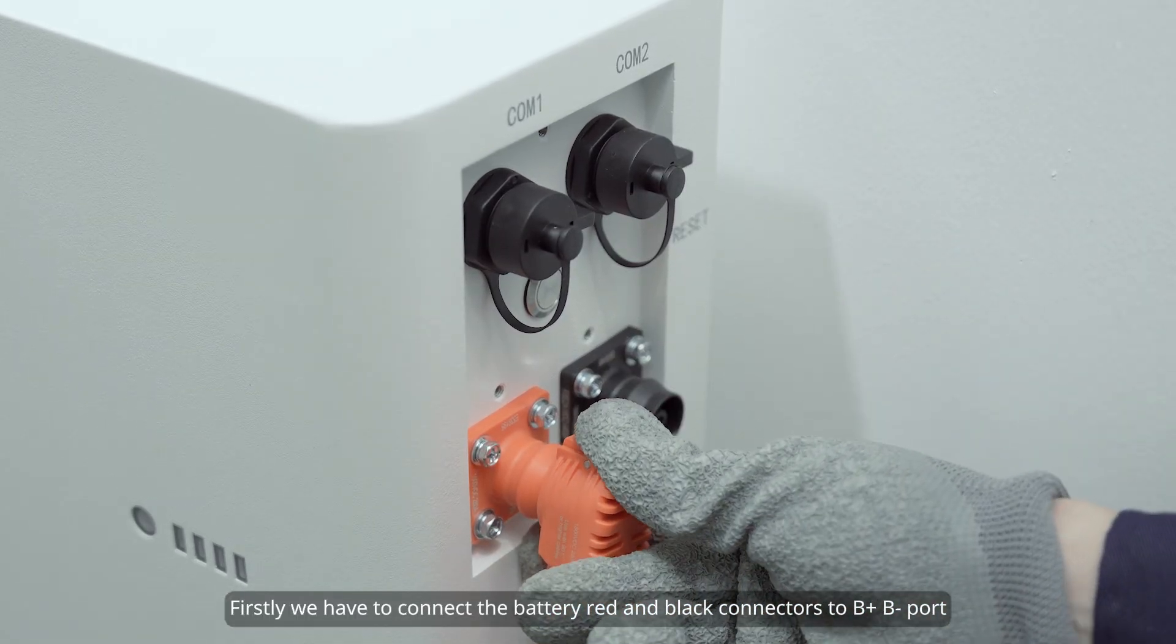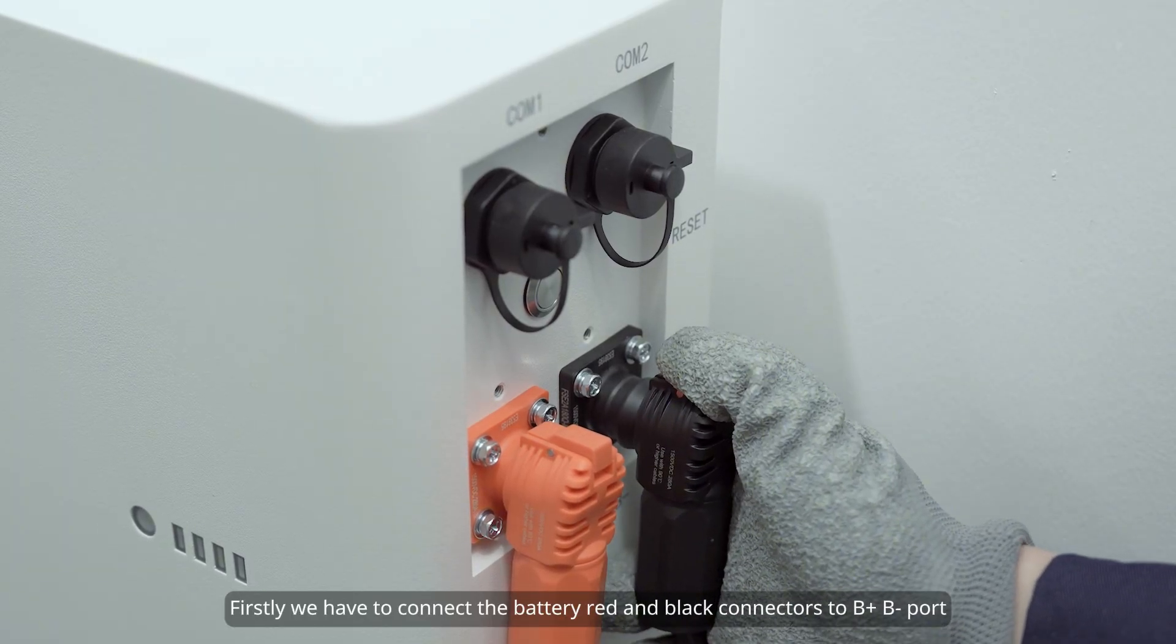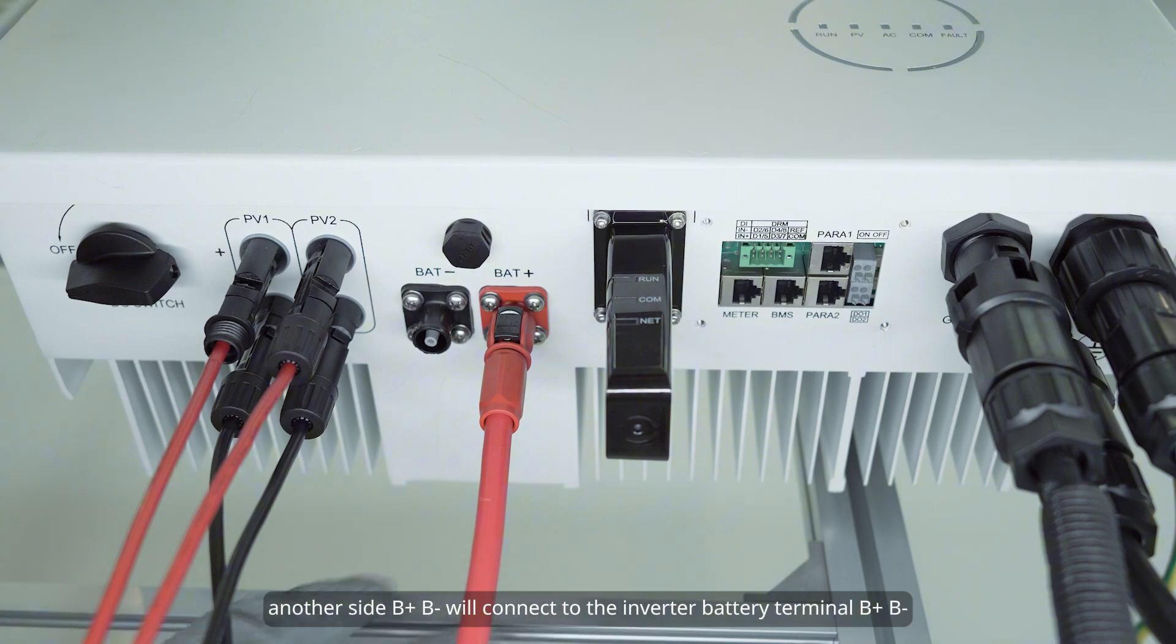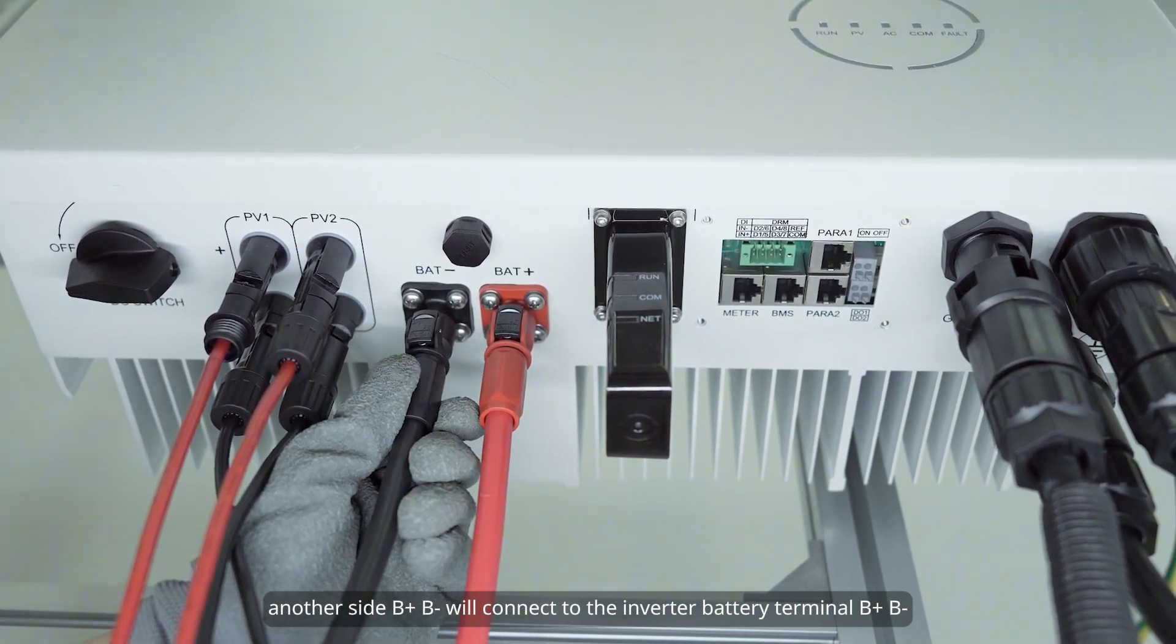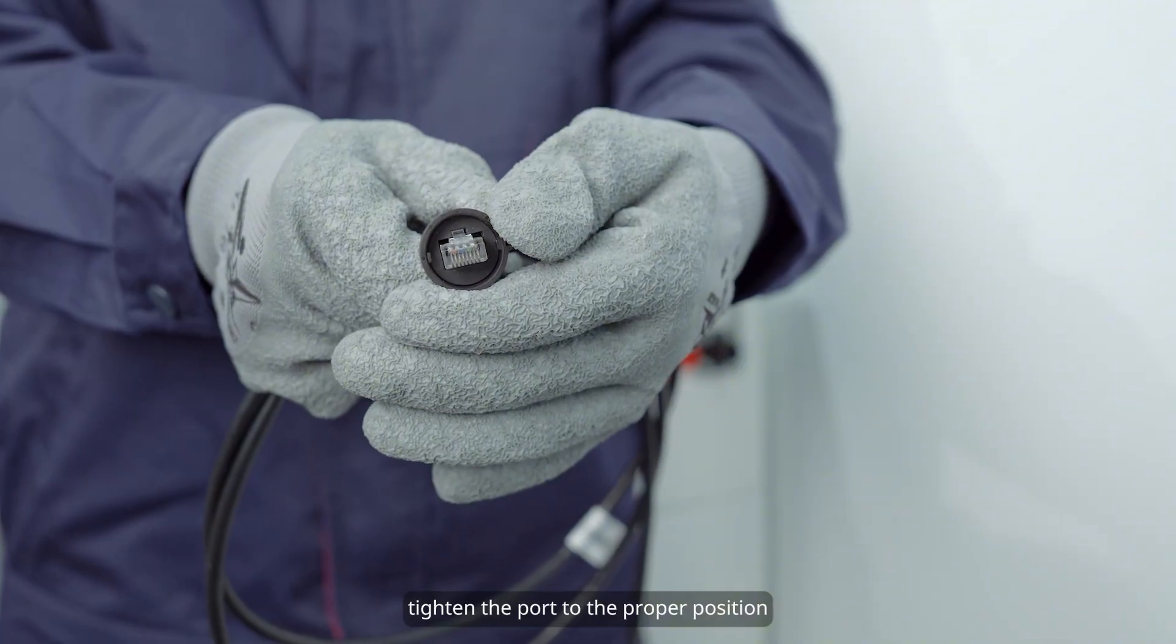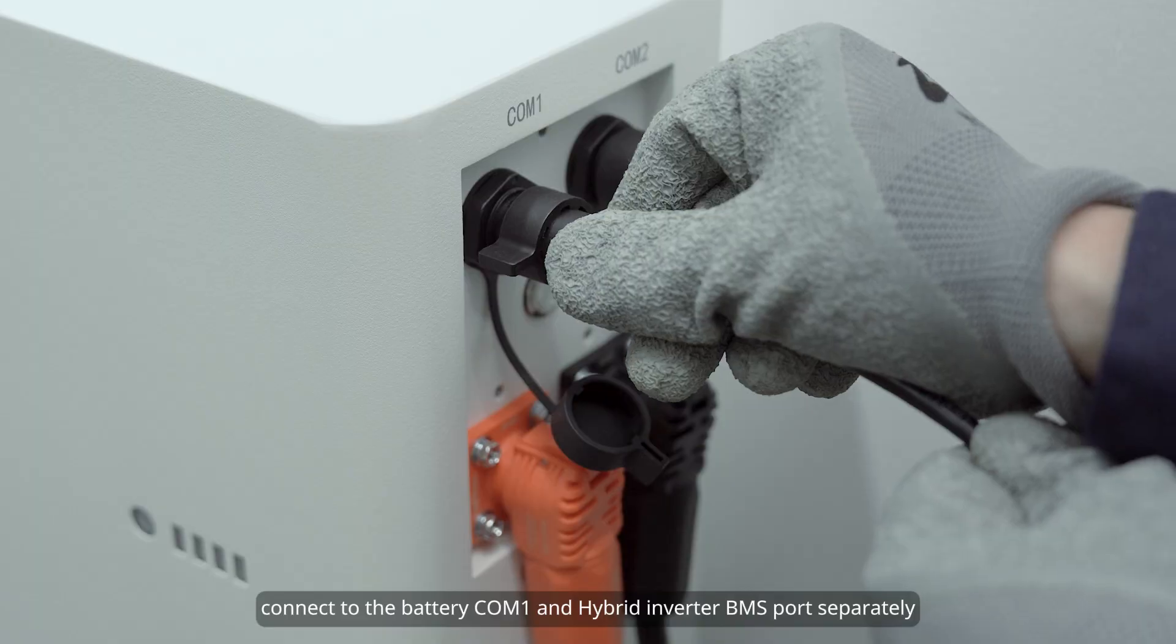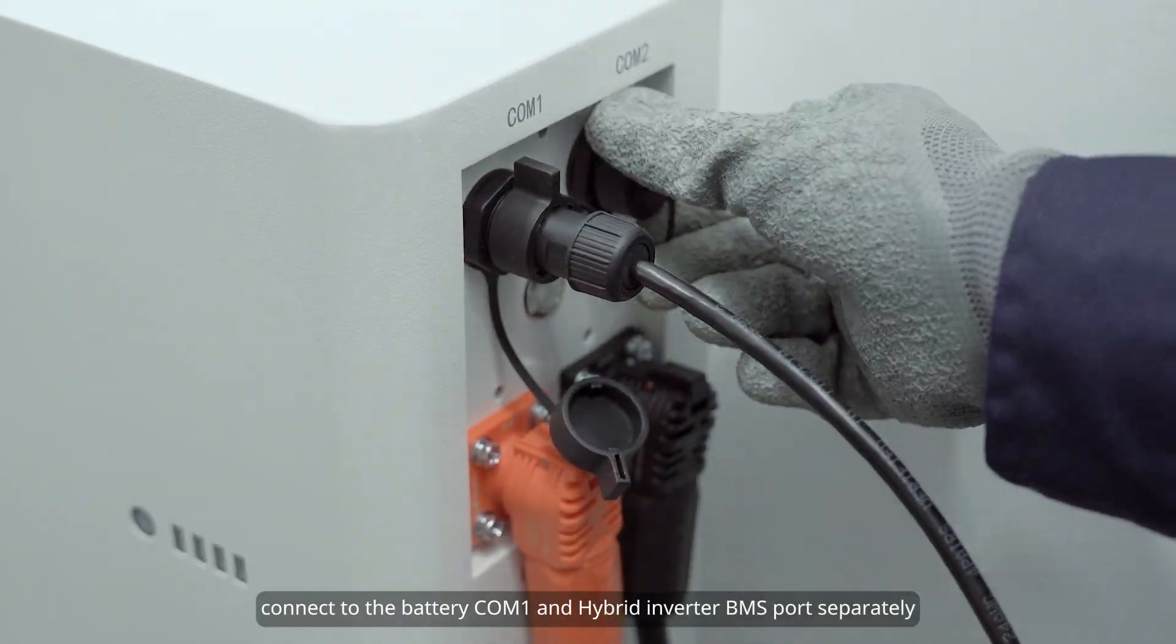Firstly, we have to connect the battery red and black connectors to battery positive and negative port. Another side, battery positive and negative, will connect to the inverter battery terminal battery positive and negative. Then take out the communication cable, tighten the port to the proper position. Connect to the battery communication port 1 and hybrid inverter BMS port separately.